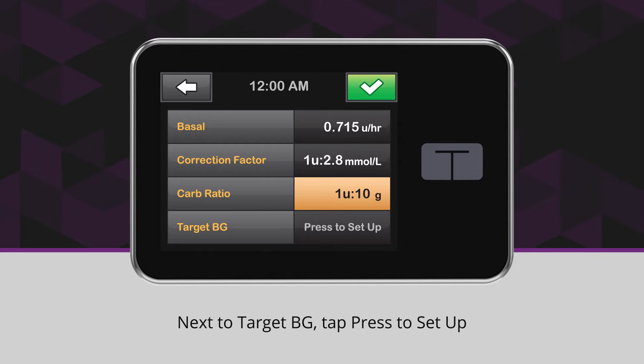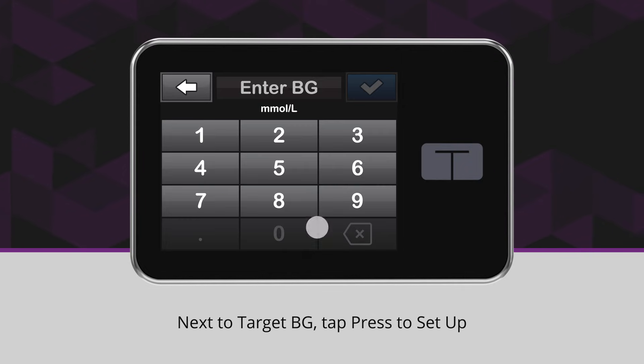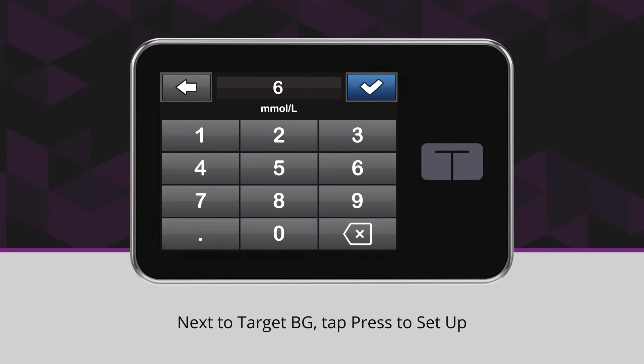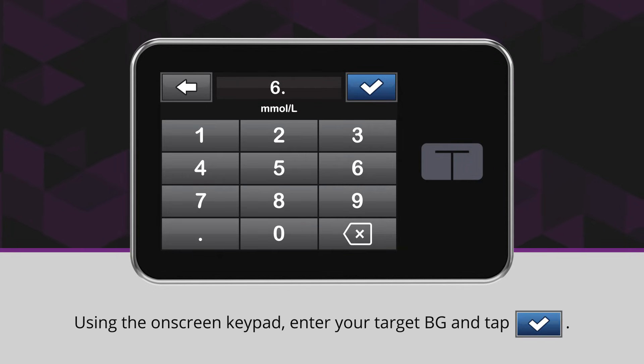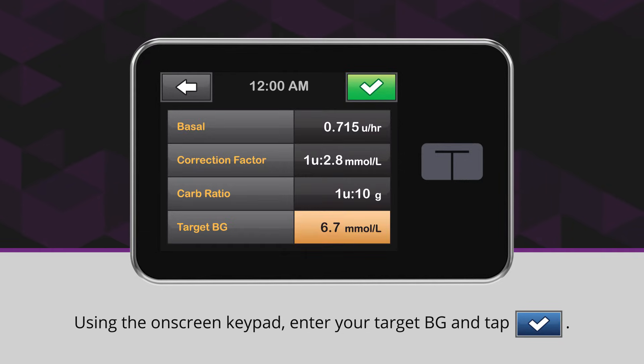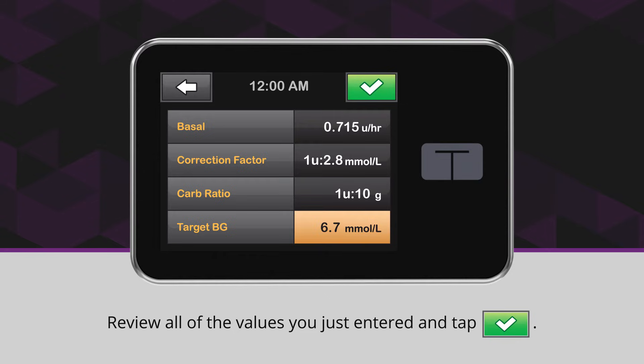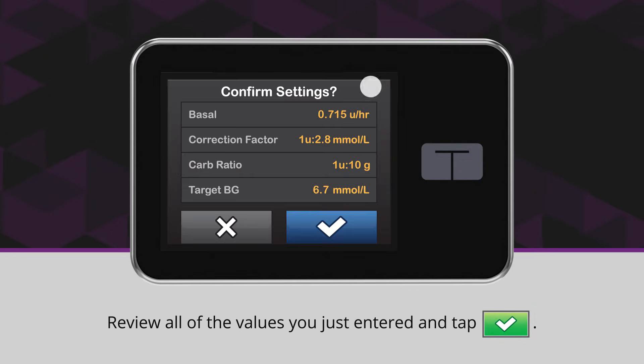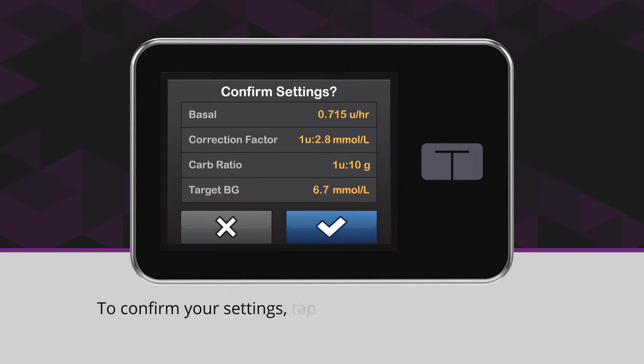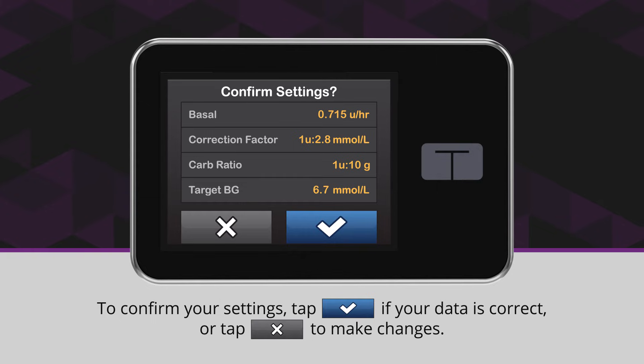Next to Target BG, tap Press to Set Up. Using the on-screen keypad, enter your target BG and tap the blue checkmark icon. Review all of the values you just entered and tap the green checkmark icon. To confirm your settings, tap the blue checkmark icon if your data is correct, or tap the X icon to make changes.